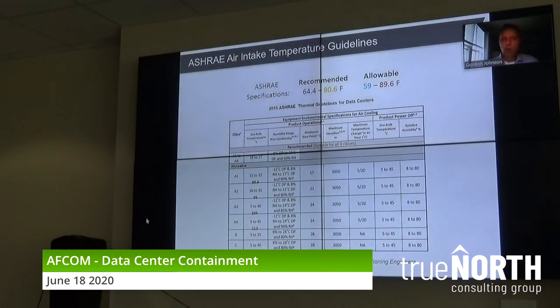That is what all IT equipment, regardless of what class it is, A1 through A4, B or C, doesn't matter. Those are the recommended guidelines, and you're not going to have any issues with your equipment. Now, I will mention you can run lower than 64. You're still probably not going to have issues, but again, you're just throwing money out the window if you do that. So we're going to focus on that high number, 80.6. They want you to raise the temperatures on your cooling units so that all of the equipment is running as close to 80.6 as possible.